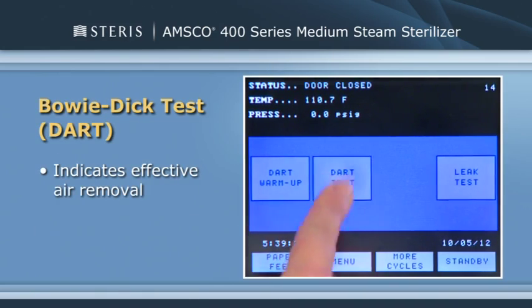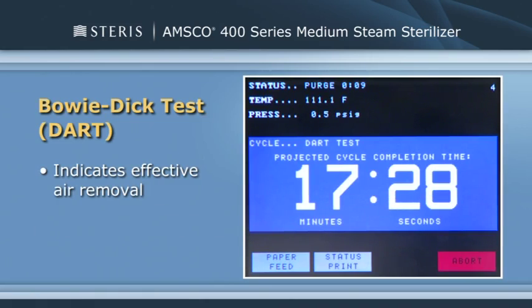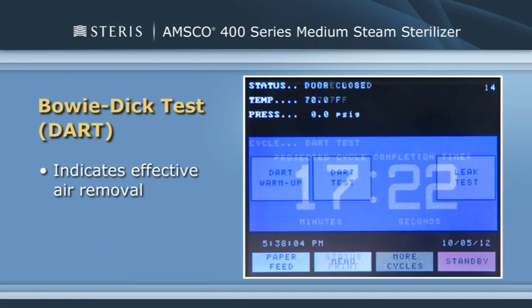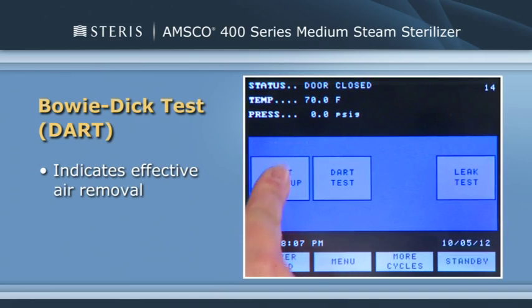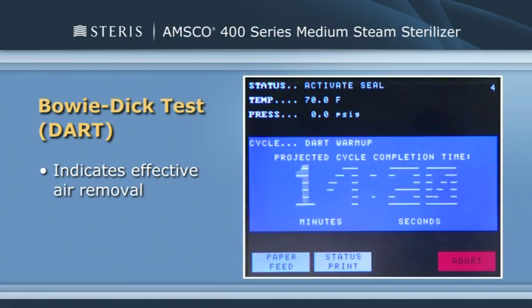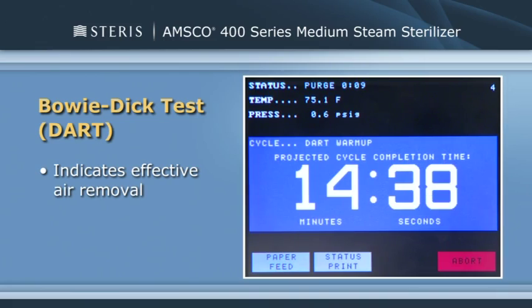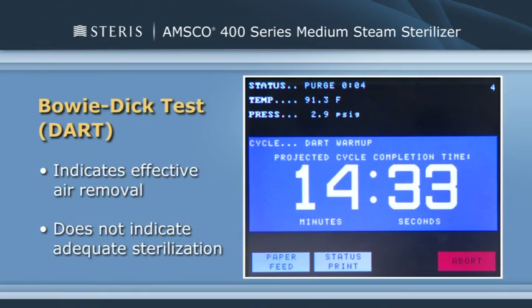The Bowie-Dick test indicates if air has been effectively removed from the chamber and challenge pack. This test should be run daily before processing any loads using a pre-vacuum cycle. To ensure valid test results, always run a warm-up cycle before performing a Bowie-Dick test to allow the machine to achieve proper operating temperature. It's important to note that the Bowie-Dick test is not a test for adequate sterilization. All test cycle values are pre-programmed and cannot be adjusted.